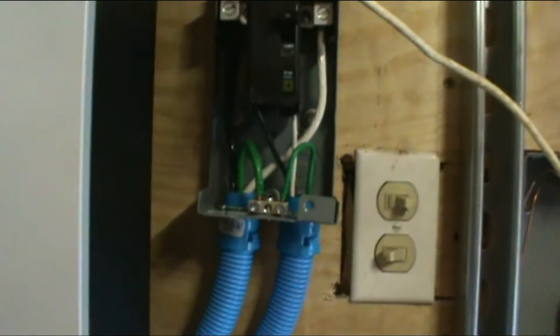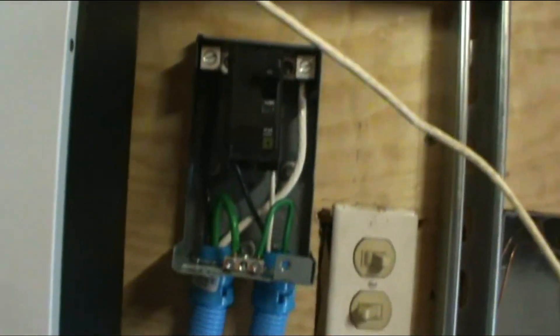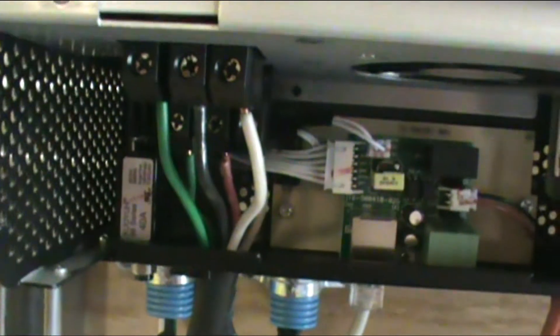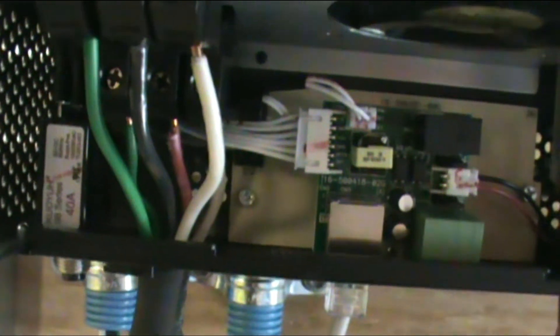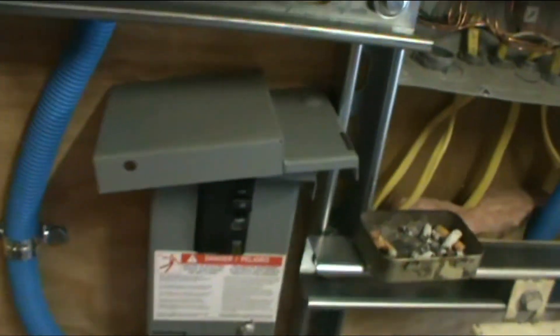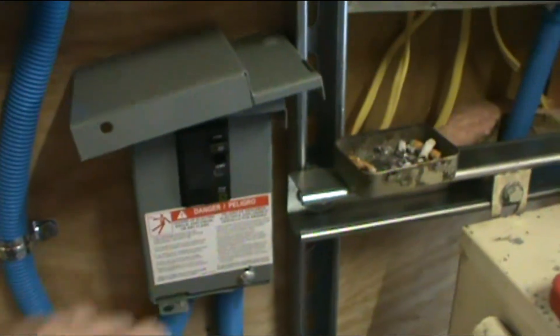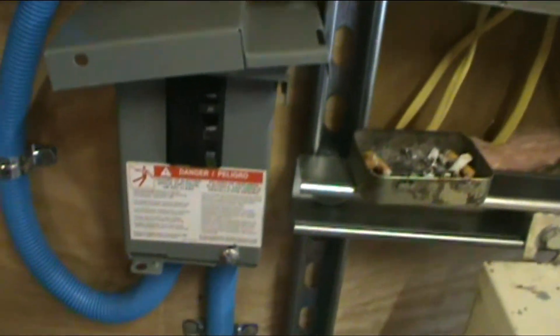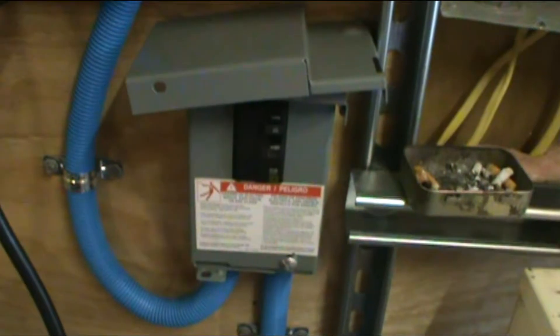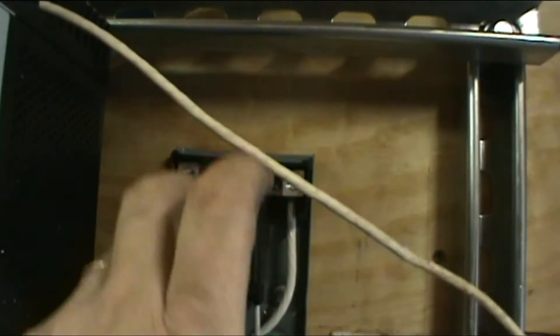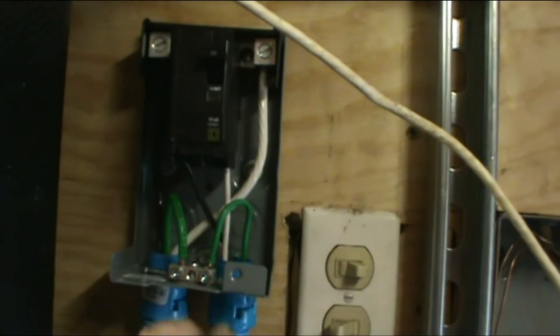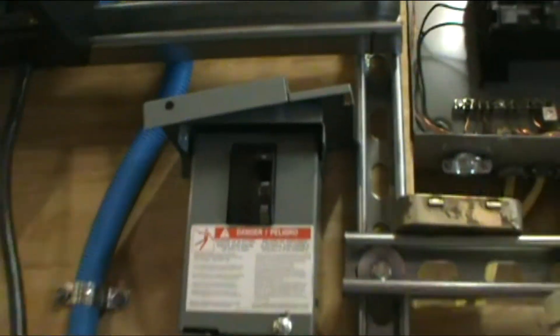The top one's your input, bottom one's your output. My output comes out of there, comes back through another piece of flexible conduit into this box. It's wired the exact same way. Since that's my output, just like coming from the transformer, it goes to the top binding post, output comes out of the breaker into this small breaker box, and then out of that breaker box we come down in three quarter inch.